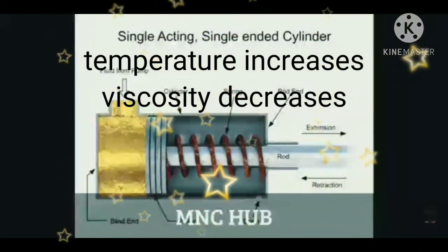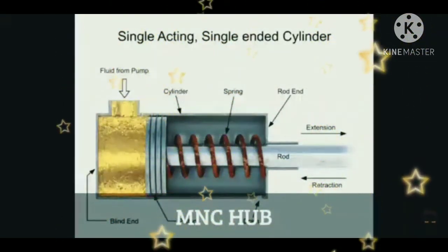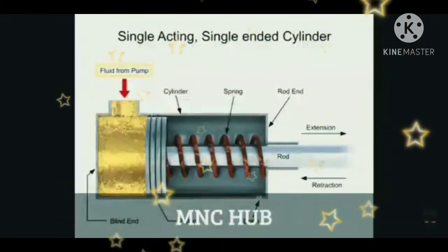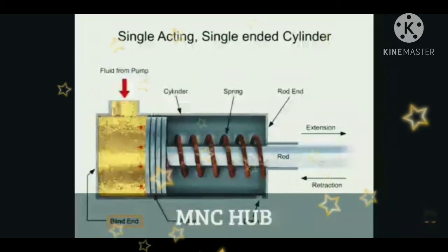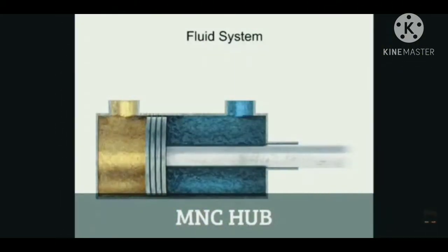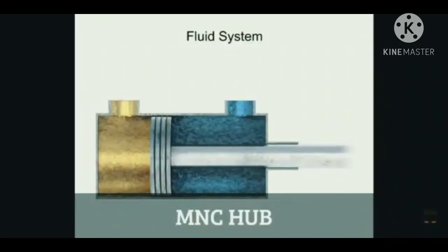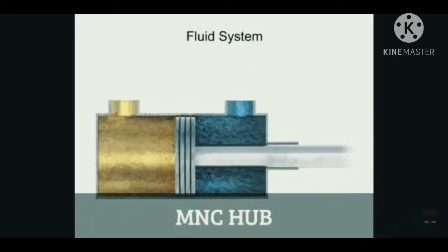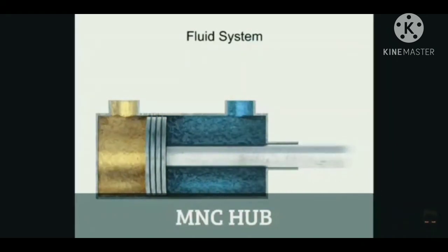If temperature increases, viscosity decreases. For example, heating the liquid makes it thin, viscosity decreases, and then it flows easily. If the liquid is too thick it offers resistance to flow and flows slowly, requiring more power, which causes power loss and excessive load. Rapid wear will also occur when the liquid is too thin. To measure the liquid's viscosity we use a viscometer.